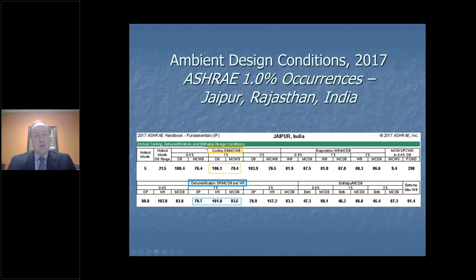What we had in the past, prior to 1997, I think I said 87 earlier, but it's 97, all we had was the cooling dry bulb with the mean coincident wet bulb. And then you had three options. If it was an extremely critical building like a laboratory environment, we might choose to use the 0.4% occurrence. And that would mean 99.6% of the year, if I used this weather data based on historical numbers from that particular city, I should be fine as far as the way I designed my air conditioning load.